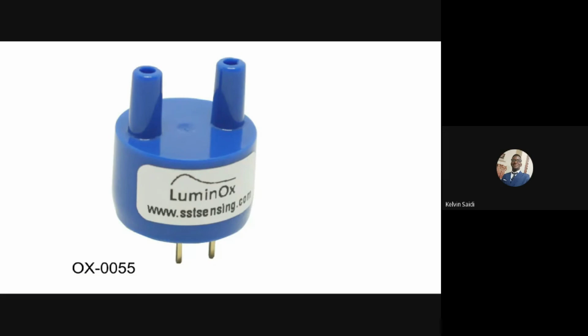Now, the last type of sensor we're going to talk about is the laser oxygen sensor. And the makeup of this laser oxygen sensor is a tunable diode laser, and they rely on spectral analysis. So a laser beam at the wavelength of oxygen is directed through a gas sample to a photodetector. So we have a principle called atomic absorption spectroscopy, and the first basic principle of this theory states that when light of a particular wavelength is exposed to particles of the same wavelength, that light is absorbed.